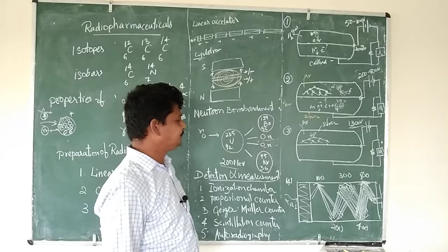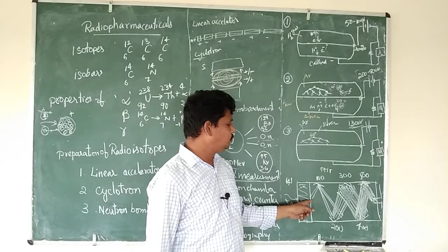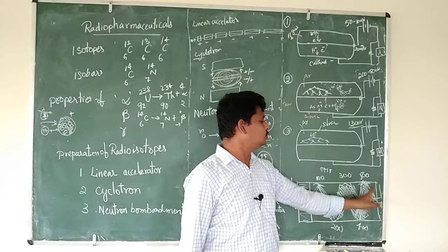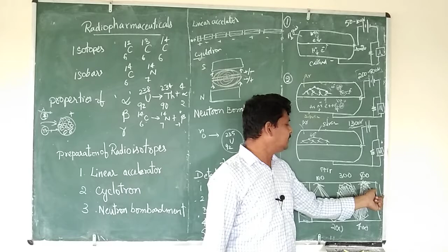Coming to the scintillation counter, scintillators are substances which absorb alpha and gamma radiation and emit photons. These photons are emitted into the photomultiplier tube, where the light is multiplied. For example, if there are two rays, different potential differences are maintained. Because of the potential difference, they are multiplied 2 to 4, 4 to 8, 8 to 16, 16 to 32, 32 to 64. So the intensity of the light is enhanced. Depending on the intensity of the light, we can find out what radiation is present. So this is how we detect.